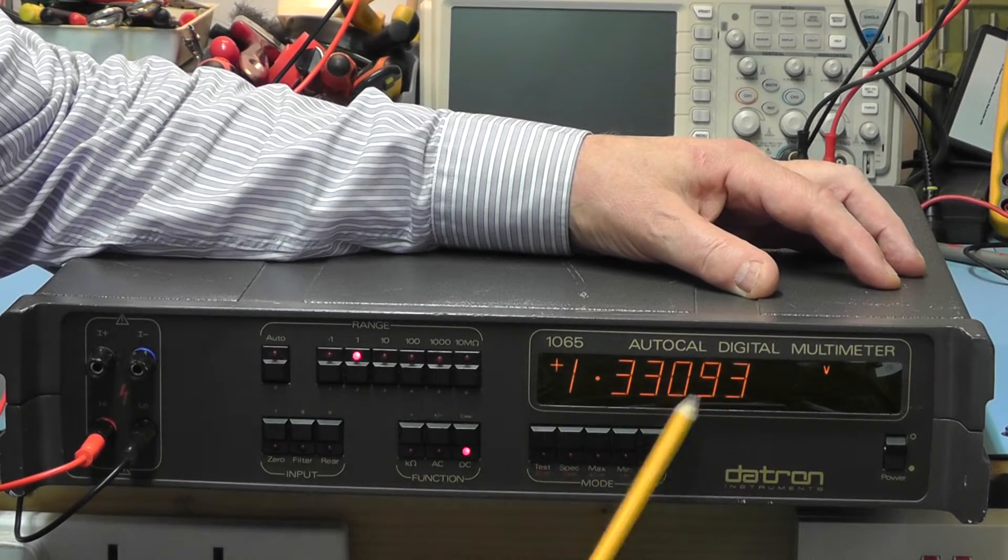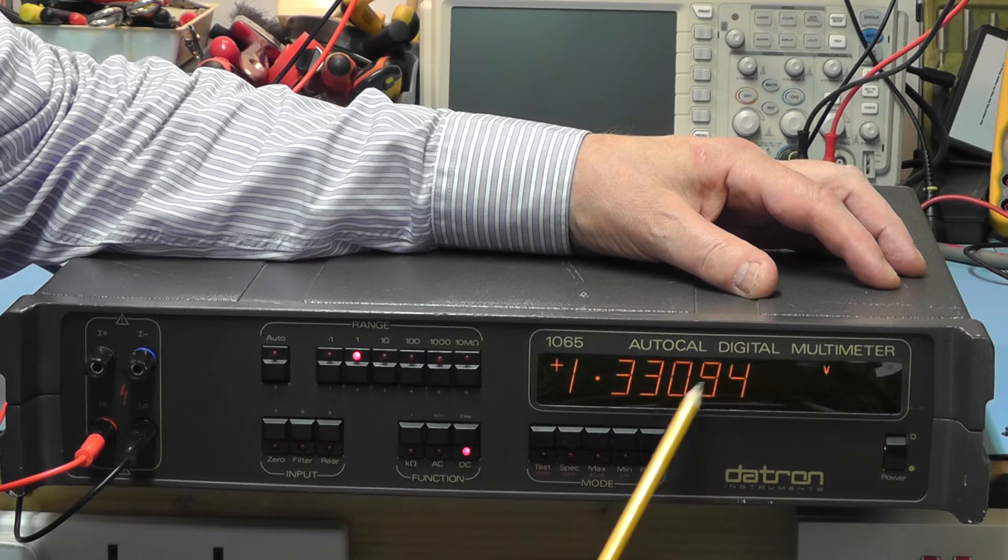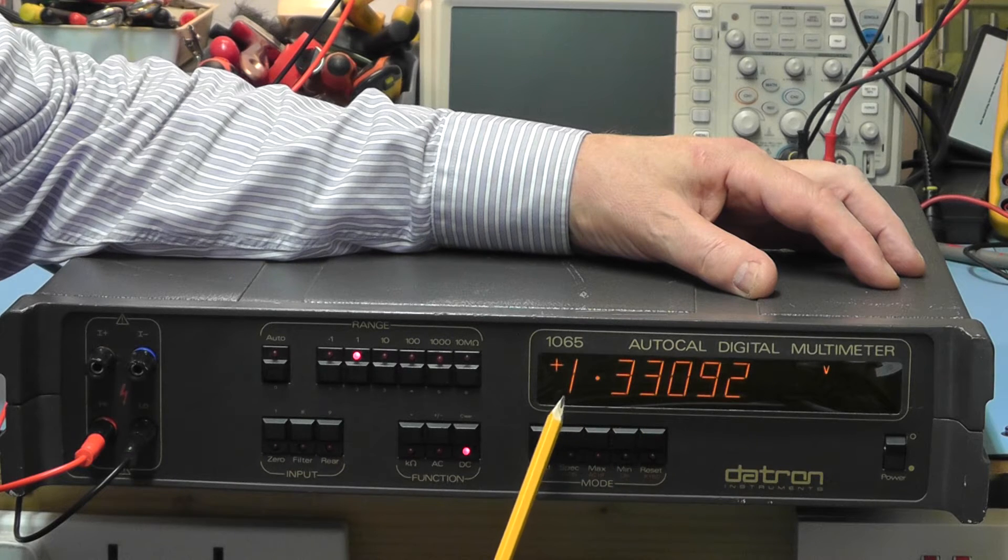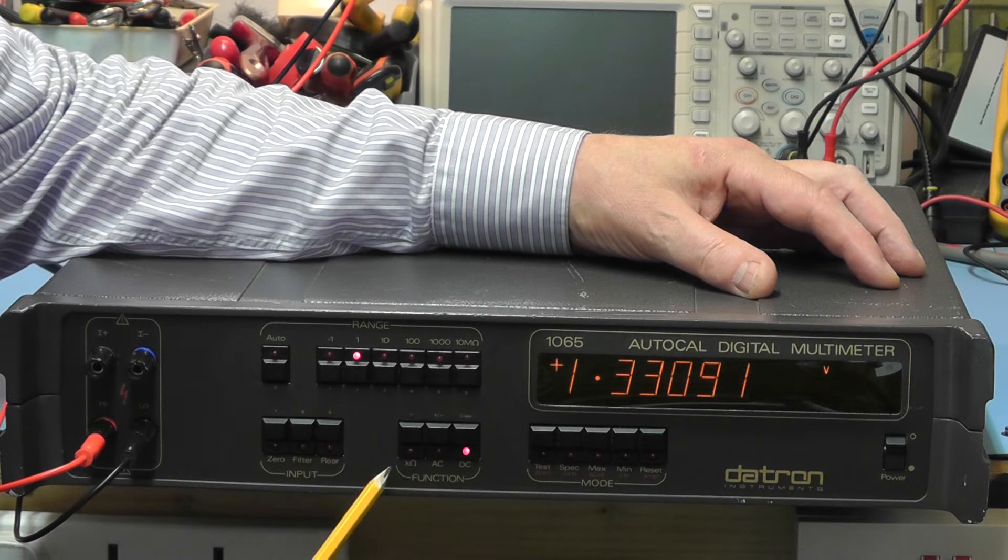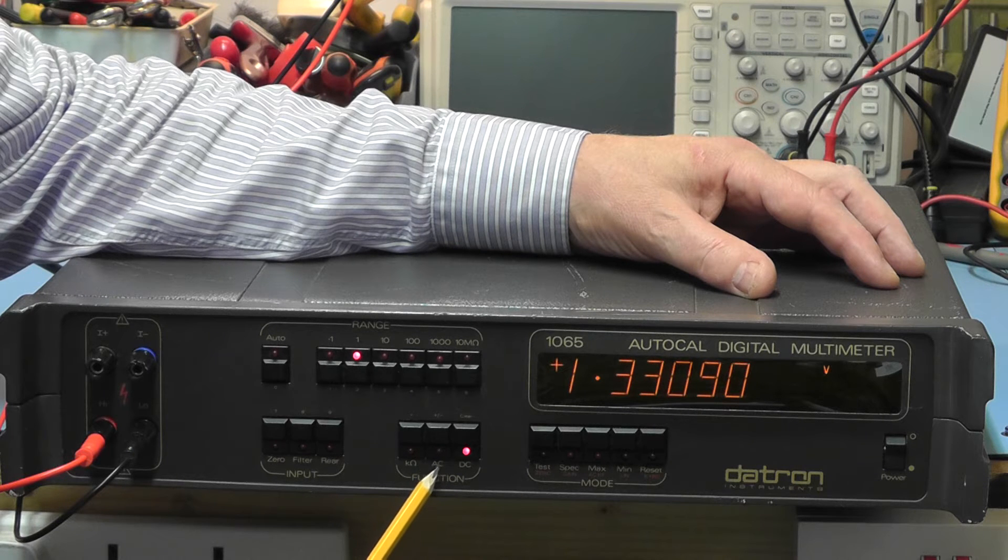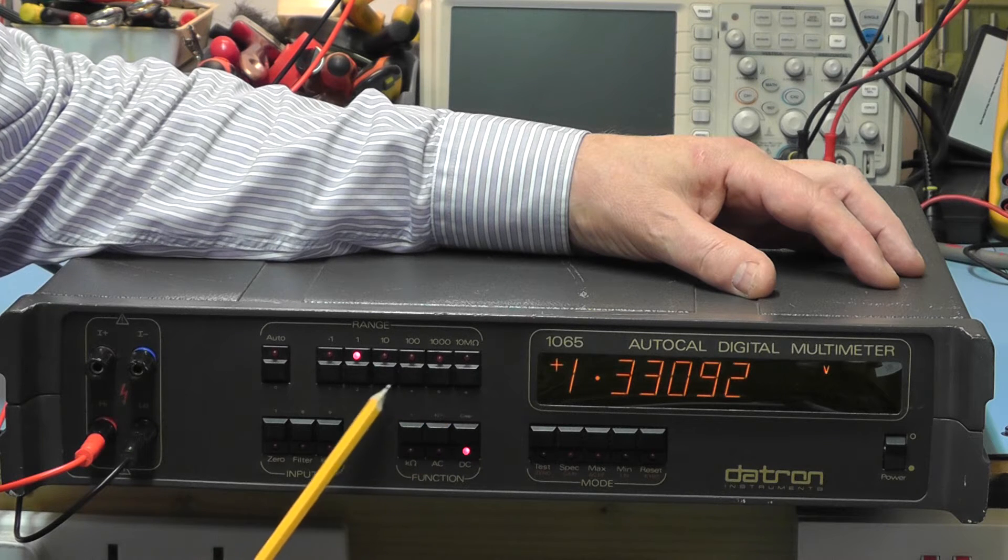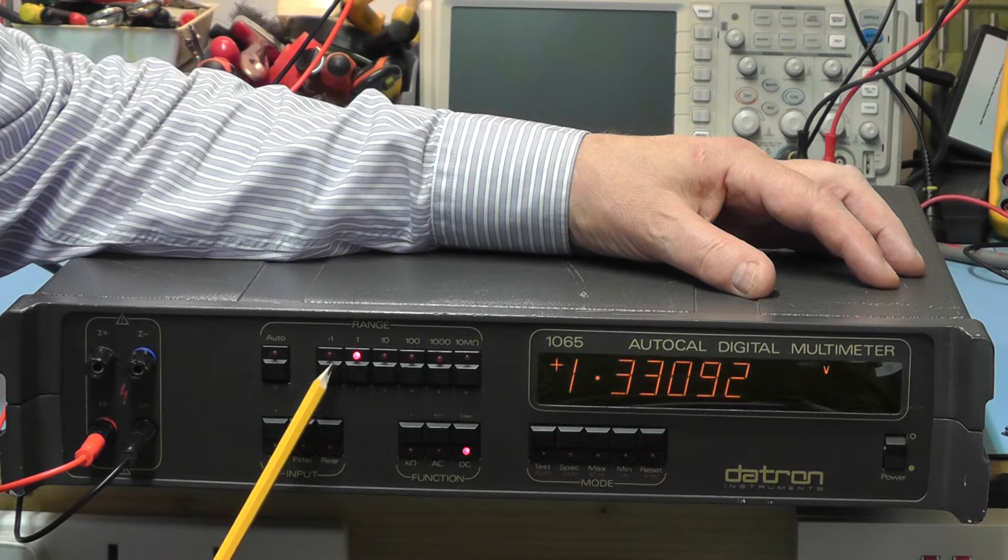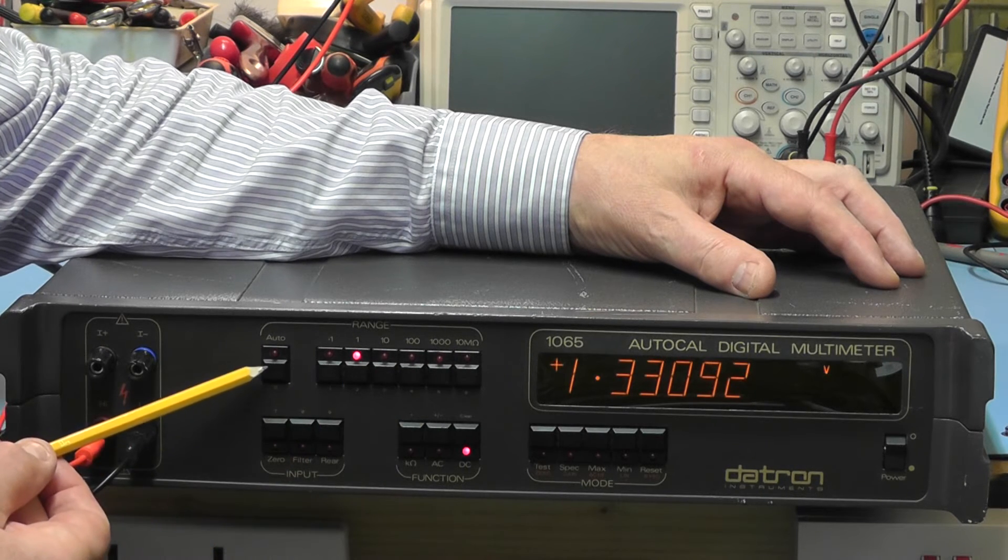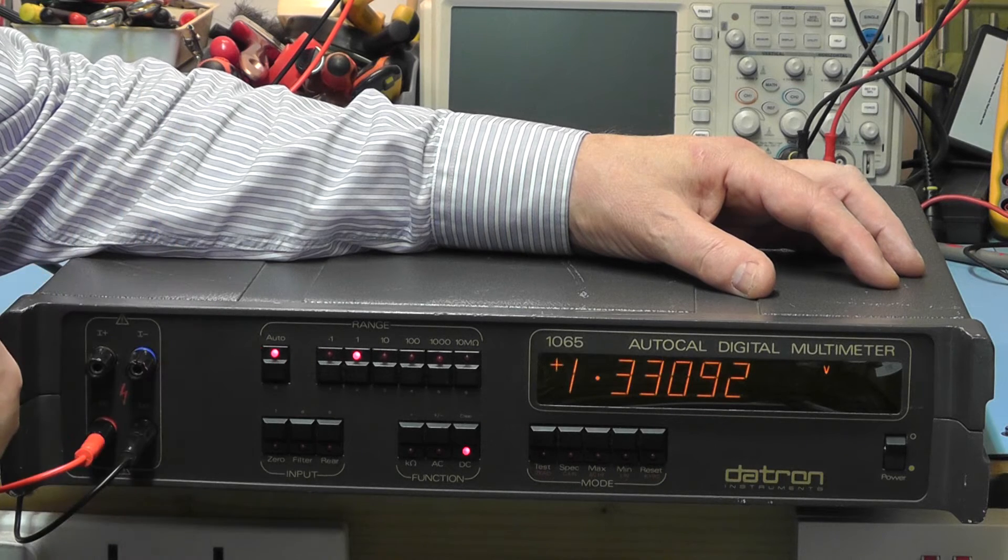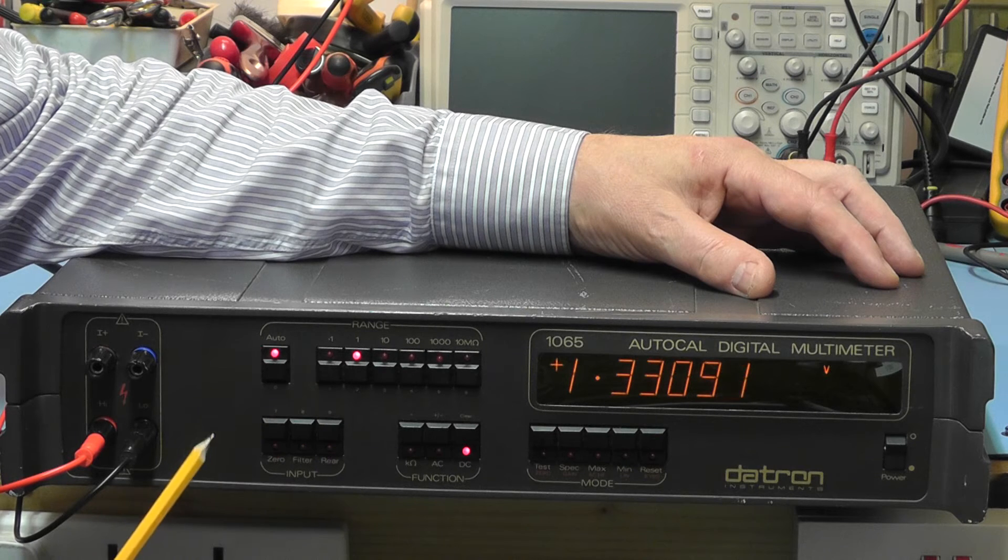Here you can see the 5.5 digit plasma discharge display, it's an orange display. Down here in the middle we have the main function buttons: DC, AC, true RMS AC voltage and ohms button. These buttons across the top here are the range buttons, the manual range buttons, but you can also select the auto range and it will automatically select the correct range for that particular reading.